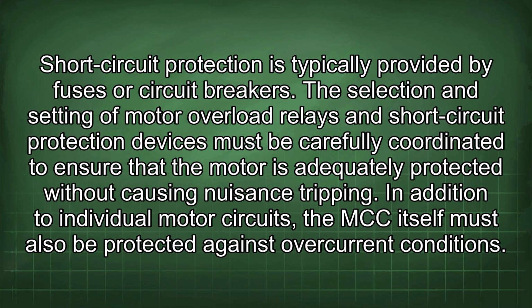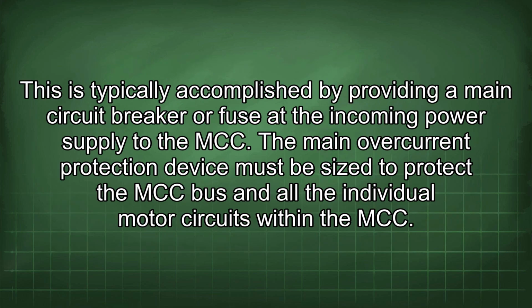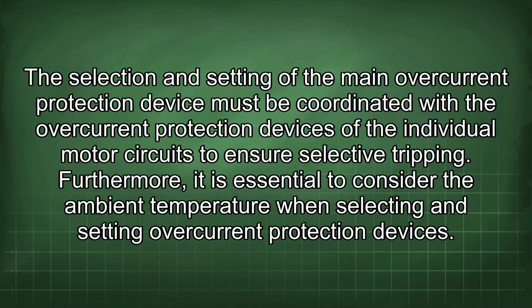In addition to individual motor circuits, the MCC itself must also be protected against overcurrent conditions. This is typically accomplished by providing a main circuit breaker or fuse at the incoming power supply to the MCC. The main overcurrent protection device must be sized to protect the MCC bus and all the individual motor circuits within the MCC. The selection and setting of the main overcurrent protection device must be coordinated with the overcurrent protection devices of the individual motor circuits to ensure selective tripping.